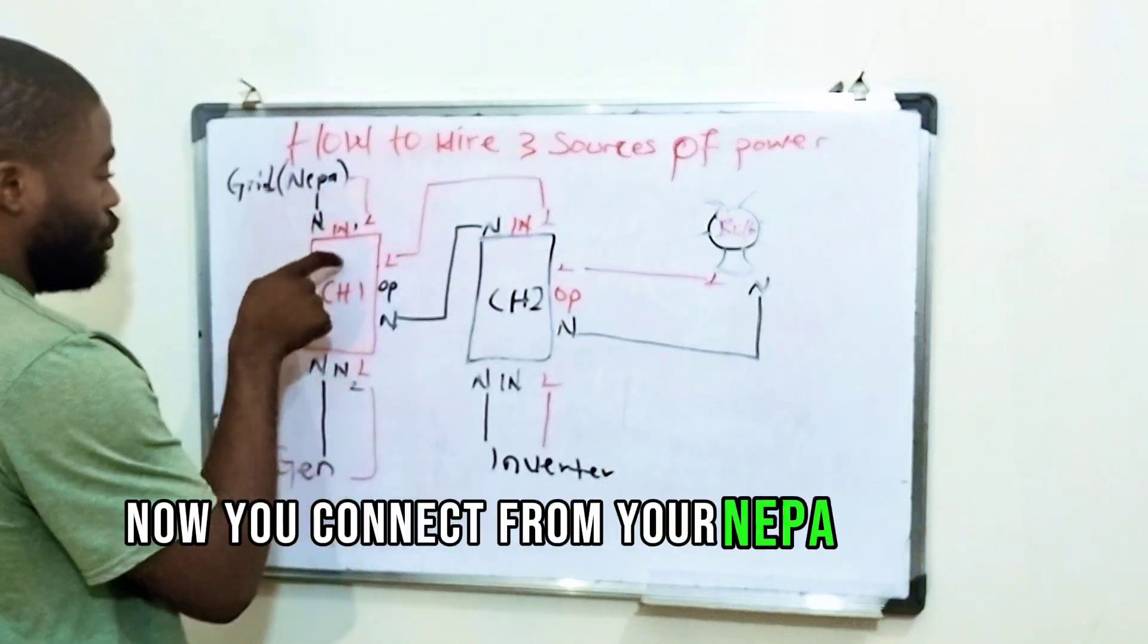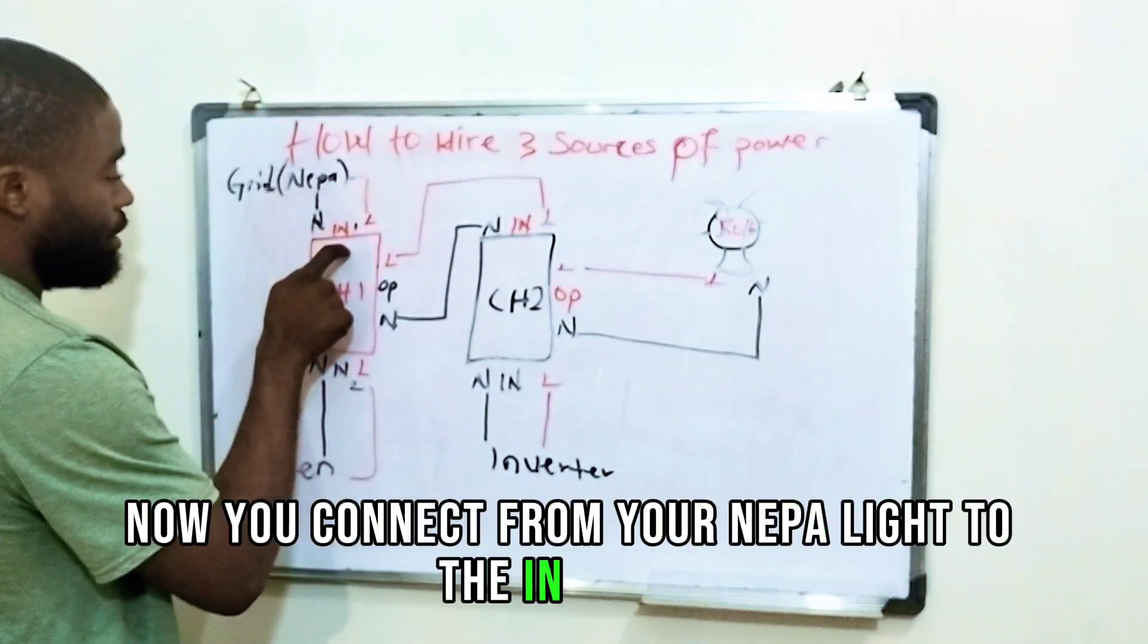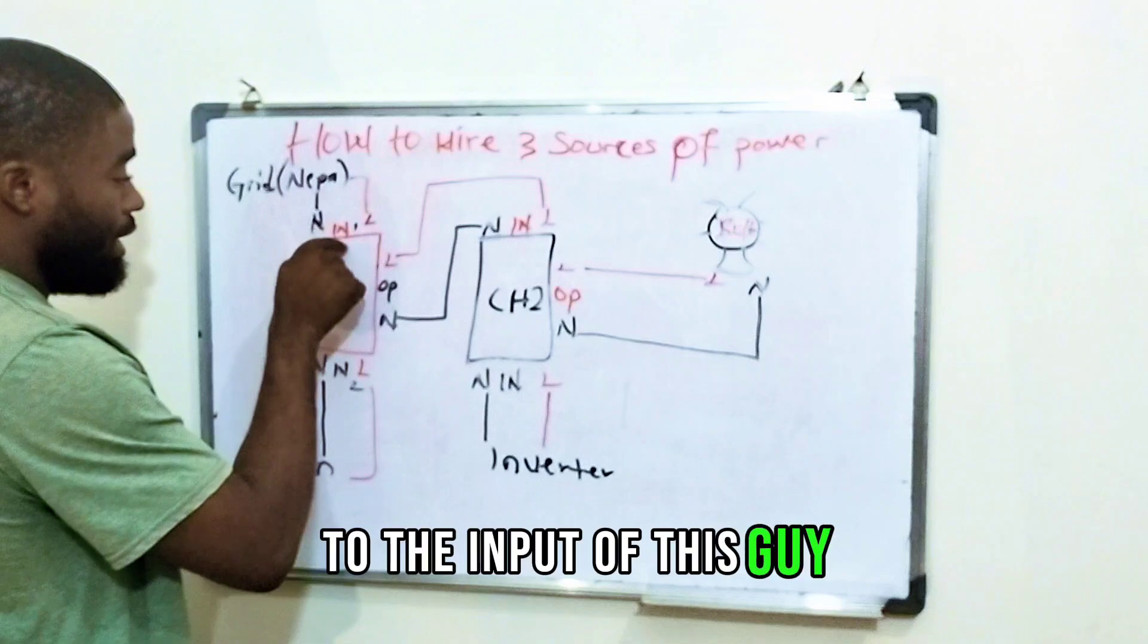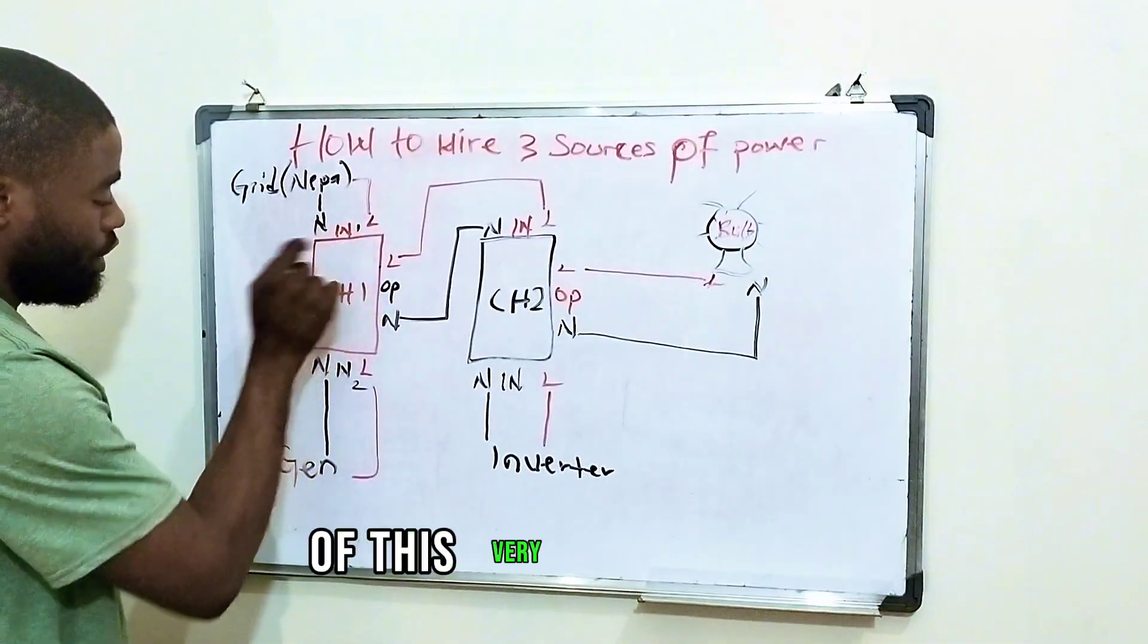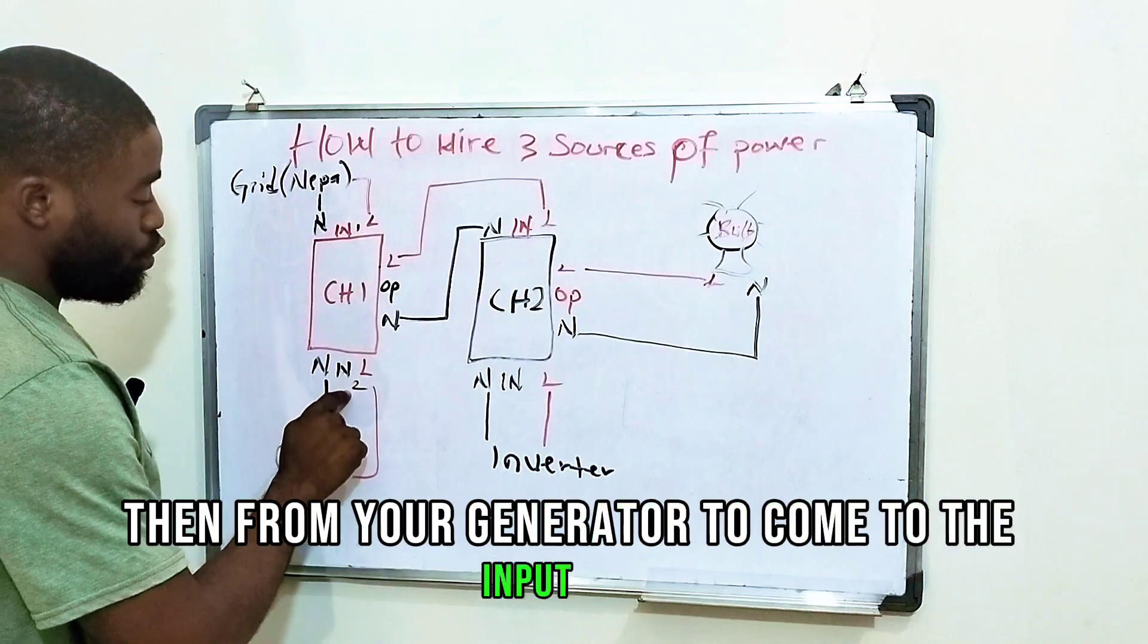Let's assume this is a hundred amp changeover. Now you connect from your NEPA light to the input of this one, let's say input one. So your NEPA will come to the input one of this very changeover. Then from your generator it will come to the input two.